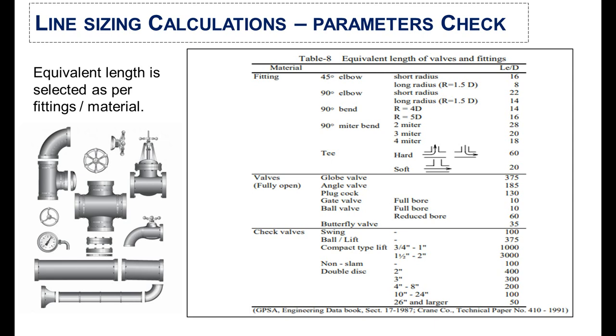Equivalent length is selected based on the fittings and materials used on the pipeline. For fittings, a 90-degree elbow with shorter radius has an equivalent length of 22. Similarly, if we add globe valves or any other type of valve, we select the equivalent length according to its type. In this table you can look up the equivalent length values according to the pipe fittings.